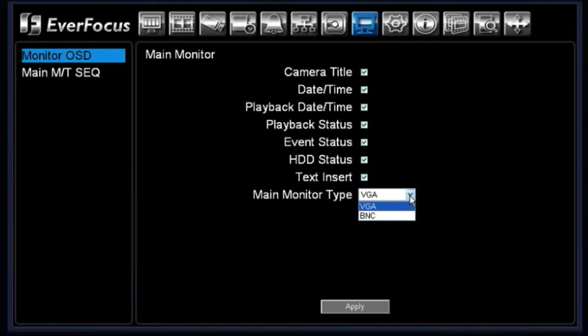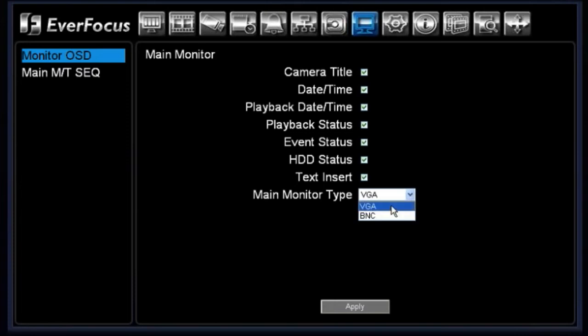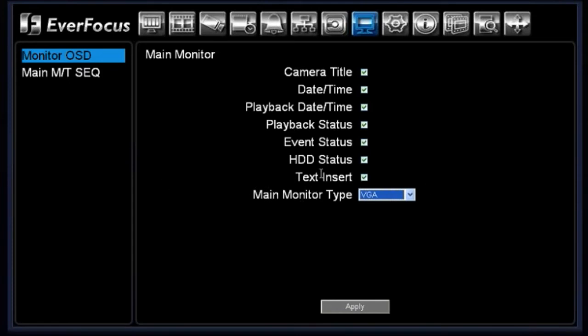You'll see under your main monitor type, you have the two different options of VGA or BNC. If you're using one or the other, you want to make sure that you choose which particular monitor you're using. If you're using both the VGA and the BNC simultaneously together, it does not matter which option you have chosen in this field.